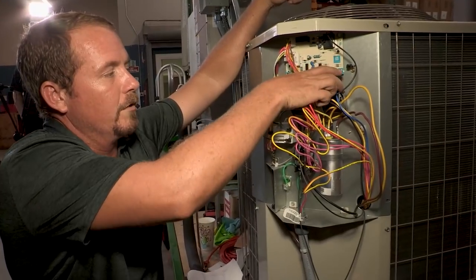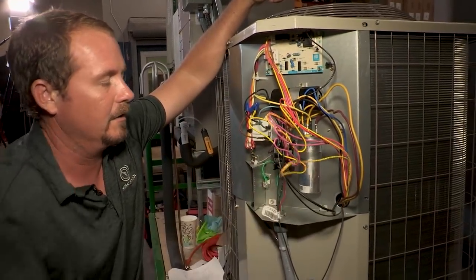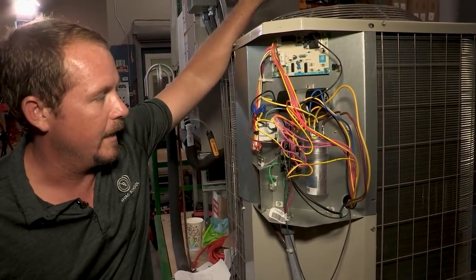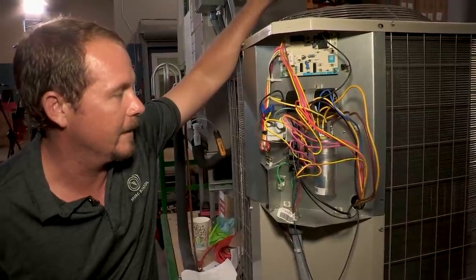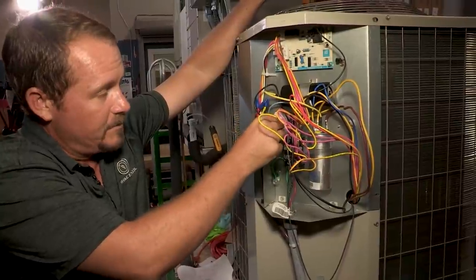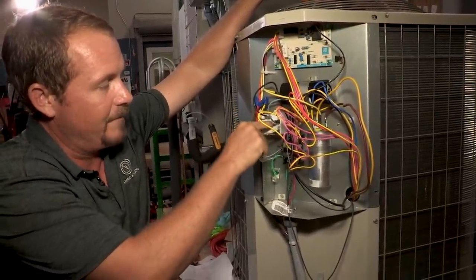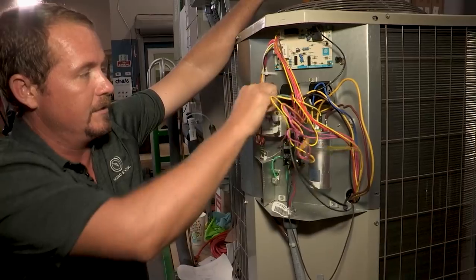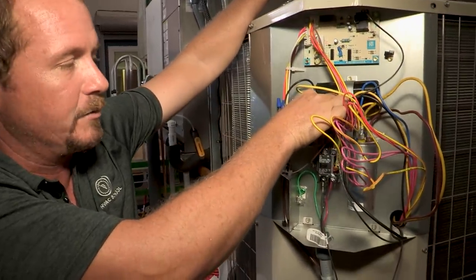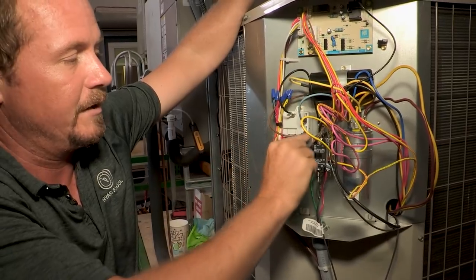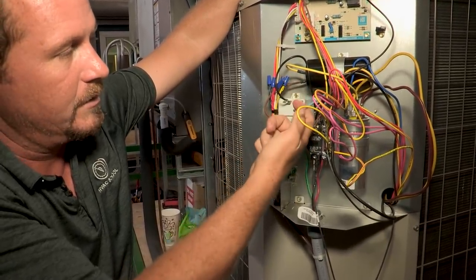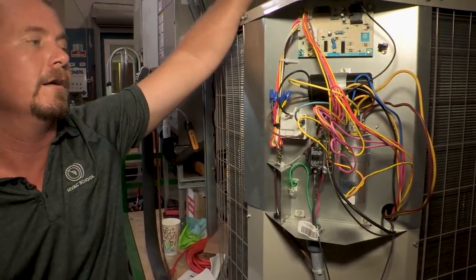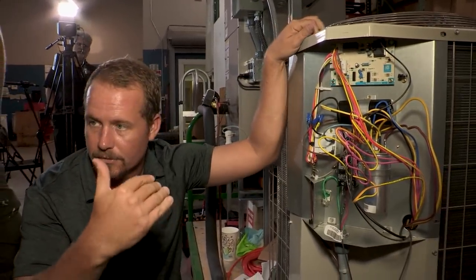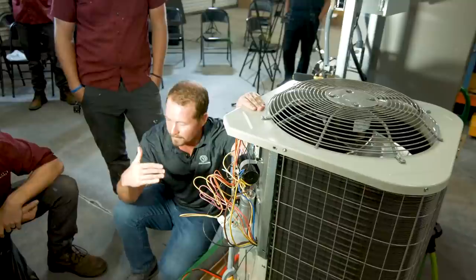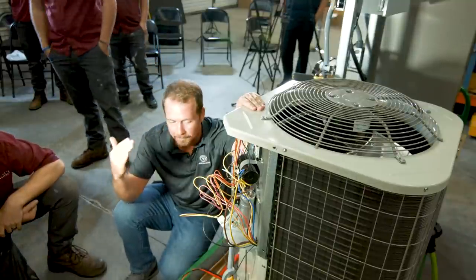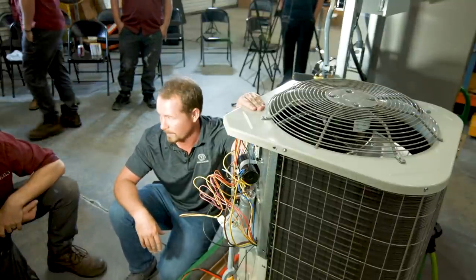run capacitor. In order for the start capacitor's capacitance to be added in parallel with the run capacitors, this switch closes and it's added together. But it's the potential difference between terminal 2 and terminal 5, that's where the actual relay coil is. Because it's a three-wire setup, it's the difference between our common side and our start side, the difference in potential there, that starts off with the switch closed, but when that difference in potential increases to the point that that contact opens, then it takes out the start capacitor altogether.